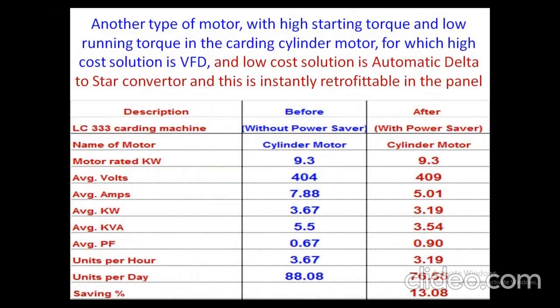By retrofitting this automatic delta-star, around 12 units per day is savable in a cylinder motor of a given machine. This cylinder motor has heavy starting torque, because the cylinder is a big size cylinder. So here it is around 12 units per day. See, a textile mill is an area where small drops make a big ocean. We can save energy in each and every motor, every machine, and every component. All these things make around 20 to 30% savings possible as such.